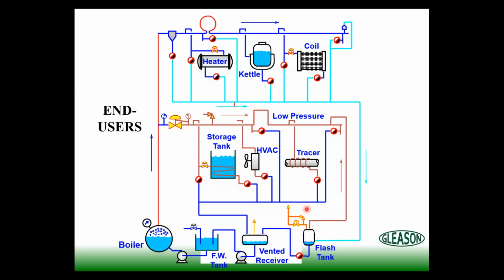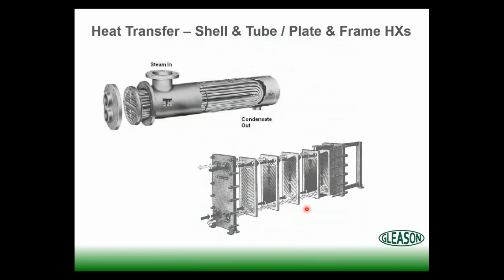So still talking about our steam loop or components within the system, let's look at some of the end users. We talked about some of the end users there. My next slide here is some heat exchangers. The old shell and tube heat exchanger, the workhorse of the steam world. They've been around a long, long time. Some very positive things there. They can handle higher pressures and higher temperatures. Some negatives when it comes to the shell and tube unit is they typically cost more, and they take up more space.